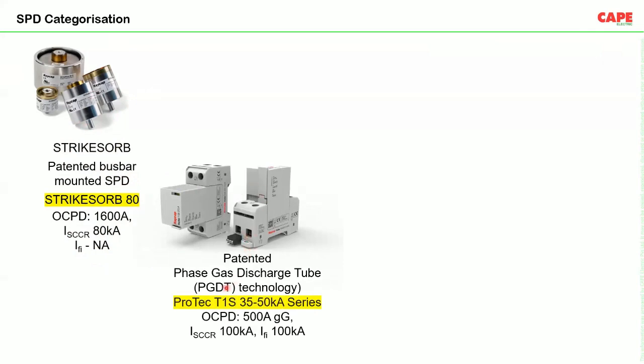The second device is called a phase gas discharge tube. The model number is this one, ProTec T1S. Here, the OCPD, overcurrent protective device, is 500 amps gG, meaning HRC fuse. Short circuit current rating is 100 kiloampere. Follow current interrupting is 100 kiloampere. Parameters of the second device.